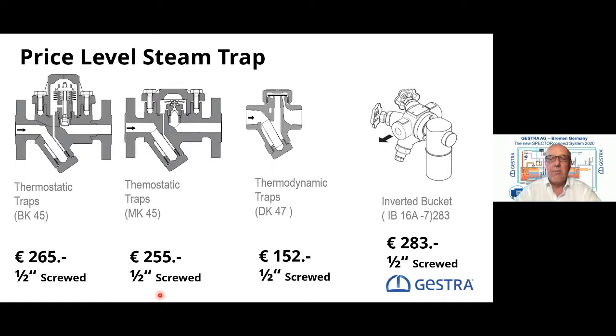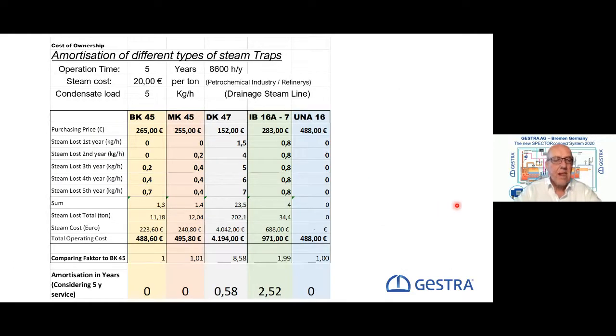But in time it changed to more important aspects in the world: saving energy, reliability, saving CO2, and easy maintenance is also very important, to have the possibility to interchange the steam traps if necessary. This spreadsheet now shows how the main types of steam trap can be compared under consideration of purchasing price and operating costs. The influence of bad steam quality and bad design of the plant is not included. We say everything is fine.